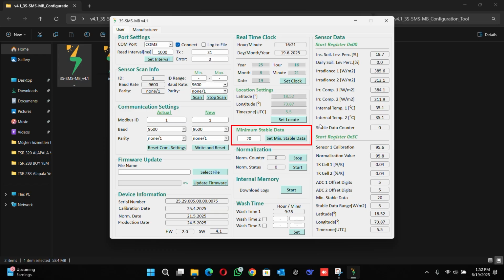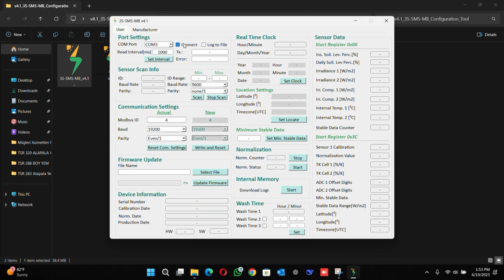The stable data is by default 20, as it's the recommended value. However, the end user is free to adjust this value to increase or decrease the precision of soiling ratio calculations. You may change device ID, baud rate, parity setting. After entering new values, click Write. If the fields turn green, the settings are saved. Reconnect using the updated Modbus values.